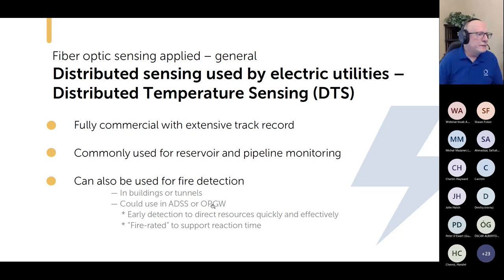An OPGW tends to be high on a structure and it's metal, so it's not vulnerable to the fire damage as much as, say, an ADSS is. But of course, nobody would like the idea of their ADSS if it caught on fire and just immediately failed. You can do fire-rated ADSS cables that would give you X amount of time, typically 3 hours. So you could get a 3-hour warning that there's a fire in the immediate vicinity of a line and make sure that resources to deal with that fire are being directed there as quickly as possible.